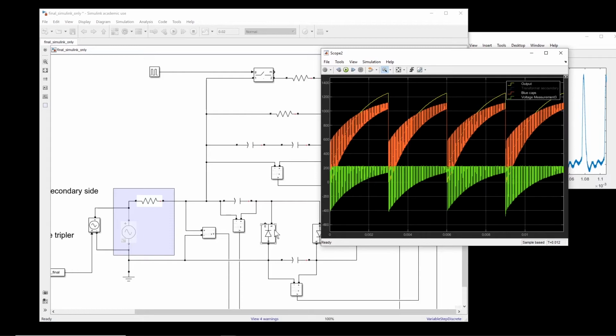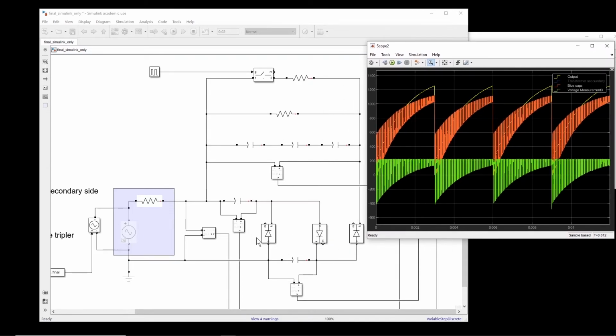Another thing to notice is that these capacitors, even if they fail, still show a value of capacitance, maybe even 60-70% of the original value, or sometimes even the same as the original value. But actually what happens is that the leakage resistance of these capacitors decreases. When you measure the leakage resistance with low voltage, you do not notice it clearly -- maybe it reduces from several gigaohms to 1 or 2 gigaohms, but you do not notice it clearly.